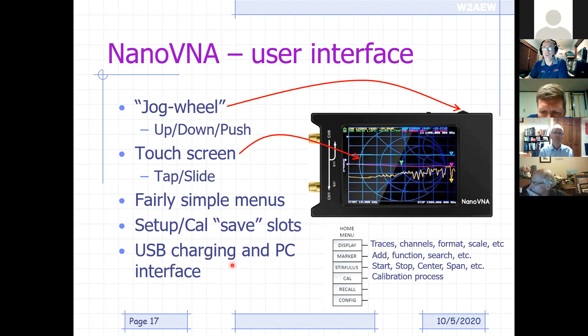There's also slots to save calibration setups so that if you make a measurement over a certain frequency range all the time, like maybe you're playing with designing a receiver and you've got a 9 megahertz IF and you're designing a filter for that and you're working on that over time, you can do one calibration over the frequency range to characterize that 9 megahertz filter, save that. So each time you power the unit up, you can recall that calibration, not have to repeat the calibration again. So there are memory slots available to save those calibration results. And of course, there's a USB port for both charging the device and to connect up to a PC with some external software.